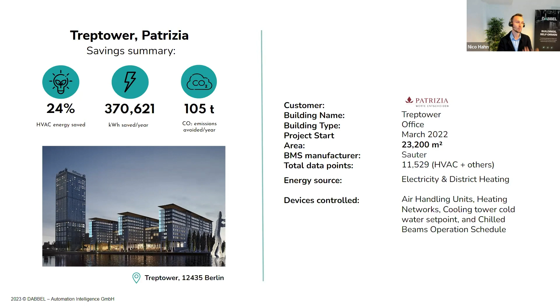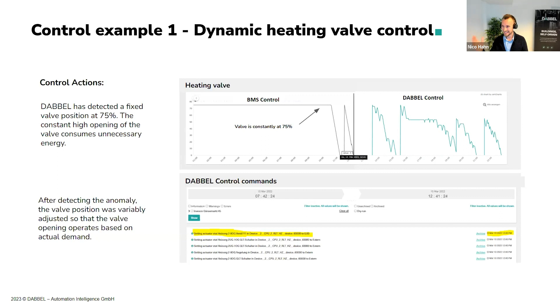We go away from a static if-else-then approach, shown on the left-hand side, where you have a constant valve opening of 75%. We transform that into a dynamic operation where we forecast the actual needs in this building, this room, this floor, for the next 60, 120, 180 minutes, based on weather data, building operation data, forecasts, and thermodynamic behavior. As shown on the right-hand side as DABBEL control, we move to dynamic operation adjusted to the needs of the building, tenants, and environment. This enables less valve opening, wasting less energy, while still achieving the same target comfort for tenants.